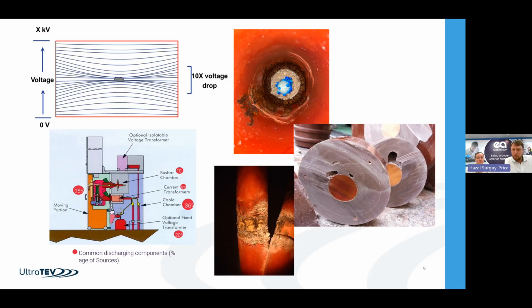The diagram on the top left is what happens when you have an imperfection in there. We look at the air void on the right-hand side, for instance. That would allow the electrical stress to build up and concentrate around that point. So rather than the electrical stress being spread evenly across the insulation, it is very much focused around a small area. That will break down, you'll have a small spark, a release of energy. That does some damage, as you can imagine, and then the whole process repeats.